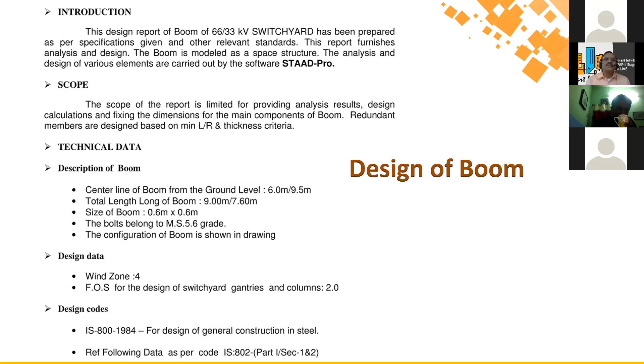So here you can see the 66 by 33 kV switchyard, analysis and design. This is the boom. We calculate the wind load and live loads. We take the self-weight of the boom, which is the weight of the angles and the weight of the cords. Then there is the electrical code short circuit force calculation. There is a formula for short circuit force, I'll explain. The loads considered are attached in the annexure here.